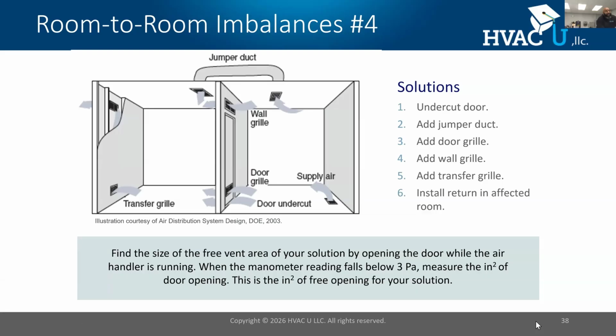So if you look here, I've got a jumper duct right here, and I'm going to connect these two rooms to get air from one location to another. Now, the jumper duct, if it's going in the attic or crawl space, is going to have to be properly sized, sealed, and insulated. So I can install a jumper duct. I can install a door grille or wall grille, properly sized, or a transfer grille to get air from one location to another. Or my favorite, if possible, is to install a dedicated return. Once I make the repair, I'm going to reperform the test and see if I can get below those 3 pascals. Really great tests, often underutilized to solve comfort problems.